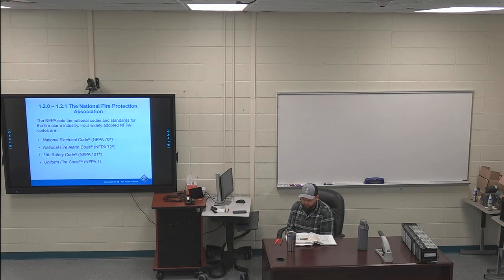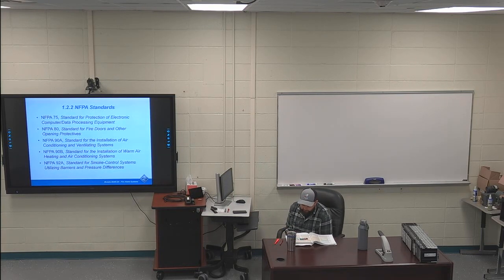And then you have standards, NFPA standards. 1.2.2. Different standards are for different things. One I've highlighted is NFPA 90A, which is the standard for the installation of air conditioning and ventilating systems. We'll talk more in the future about how back in the day they didn't have fire alarm stuff for HVAC or ventilation, and ventilation equipment could spread the fire through the ventilation system. So they had to create a standard for making sure that the air duct work and stuff like that had proper signaling for either shutting down or letting everybody know that there's a fire. So different standards for that.